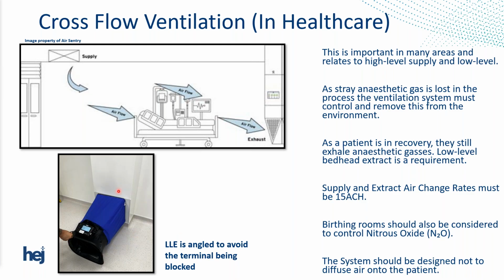This is a straight mechanical extract that we're measuring at the point of validation. You can see we've changed our balometer hood to a shorter one, so we can measure it at validation and it's repeatable every time we verify it. There are other spaces to consider too, like birthing spaces, recovery rooms, and anaesthetic rooms — these are the type of areas where we need to think about cross-flow ventilation.